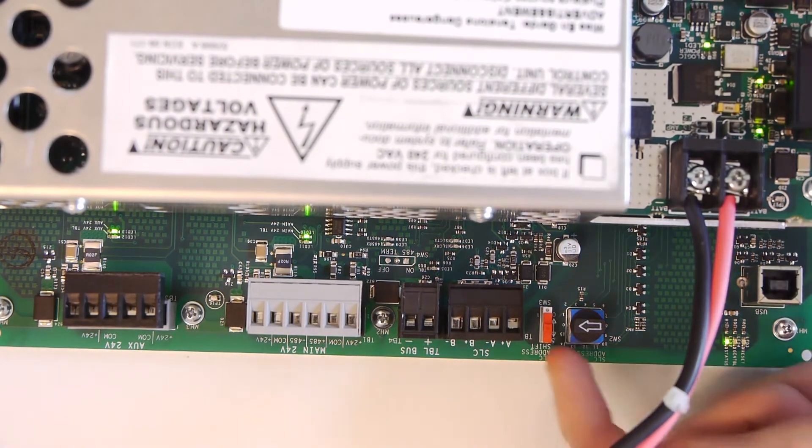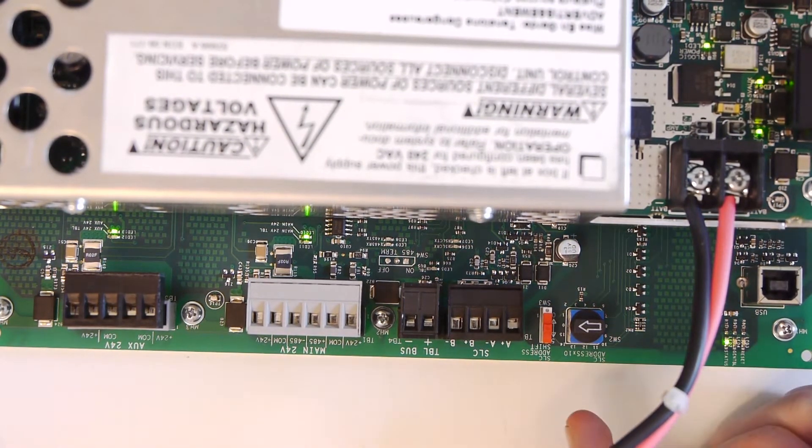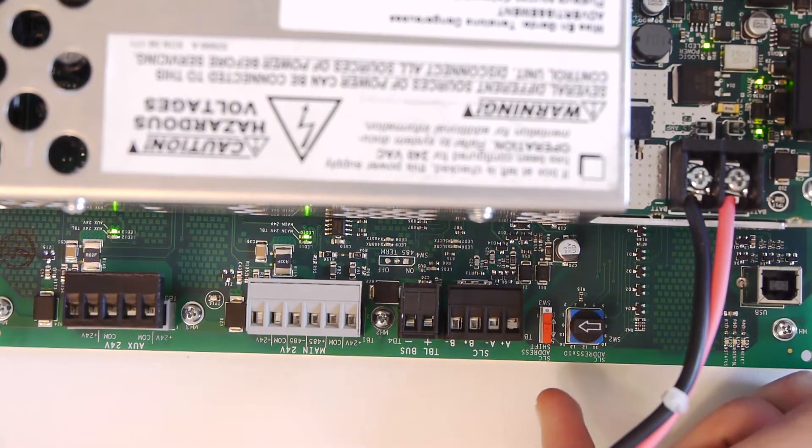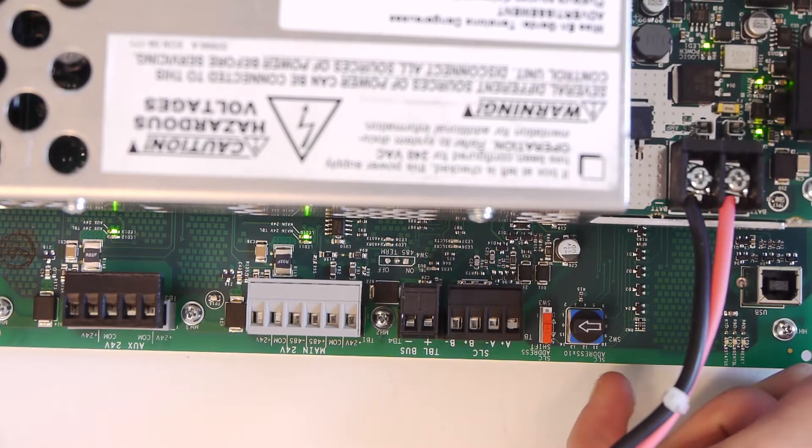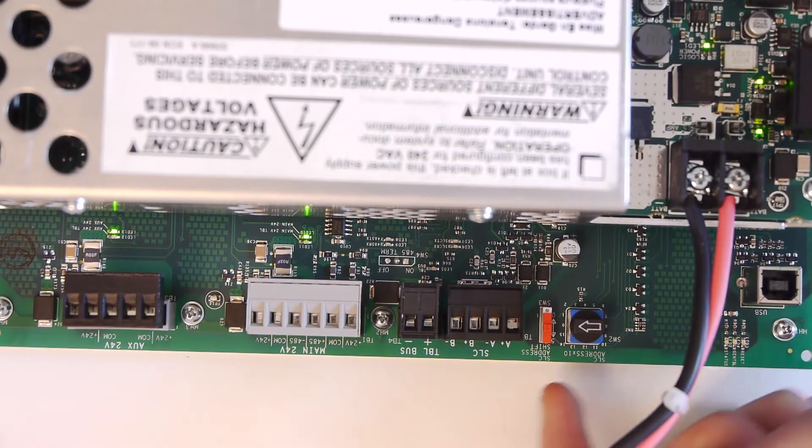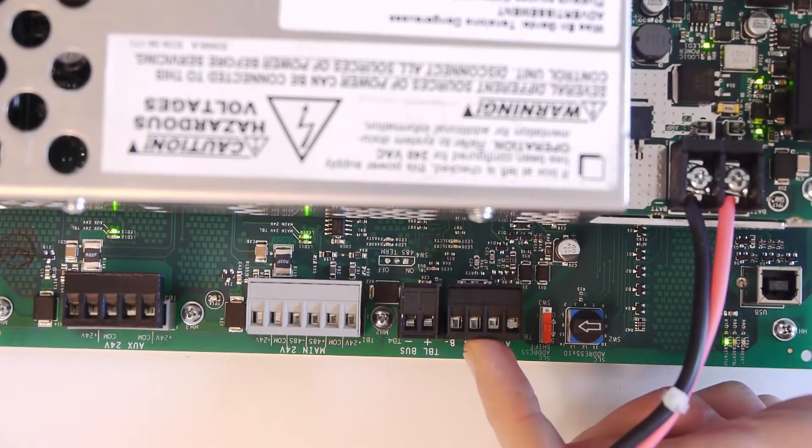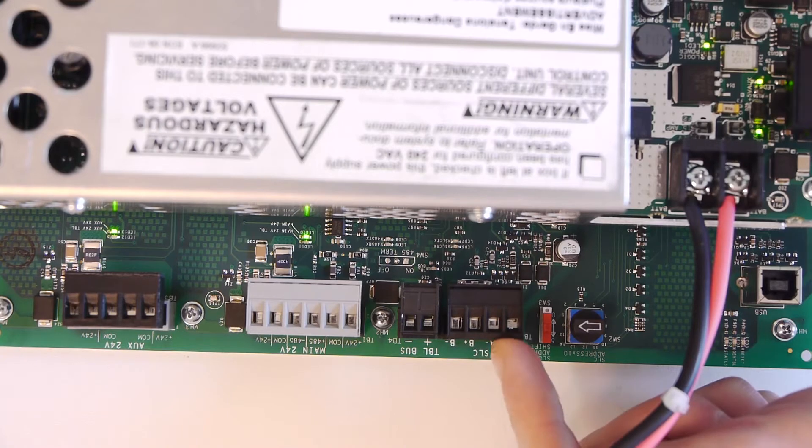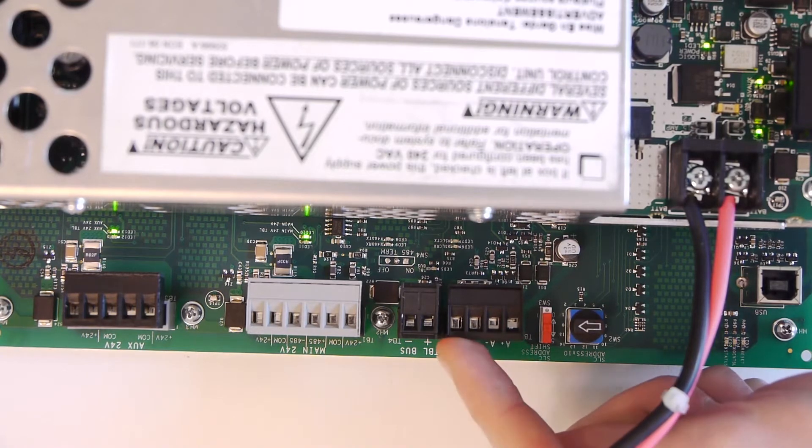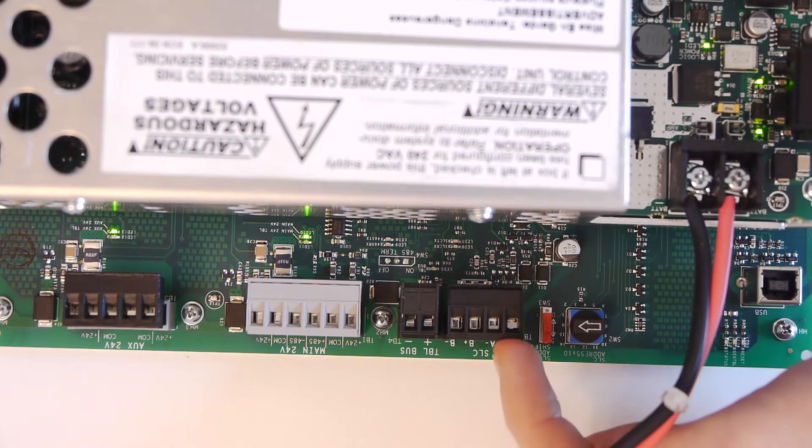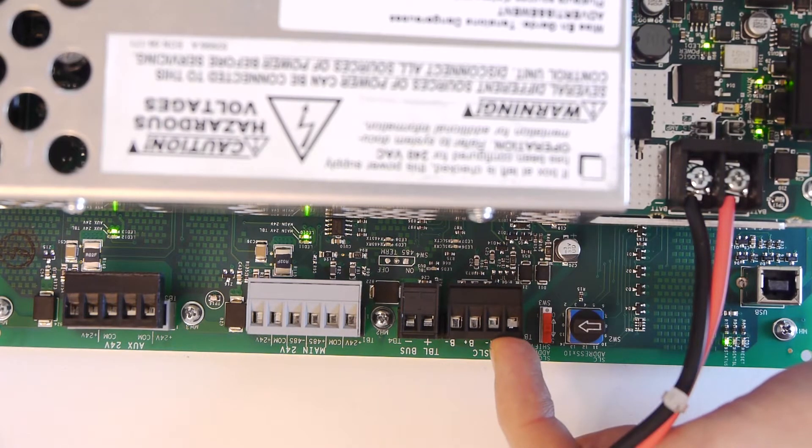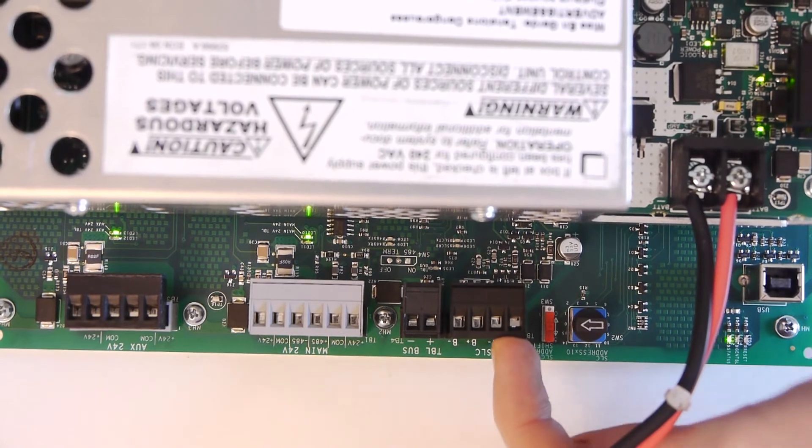Right here are two switches that have to do with the SLC address. I'll get more into that later. This is your SLC connector. It has class A, so A+, A-, B+, B-, and this is basically how it communicates with a fire alarm panel.